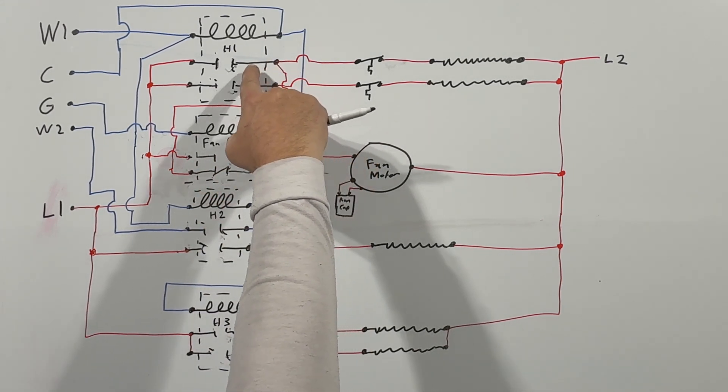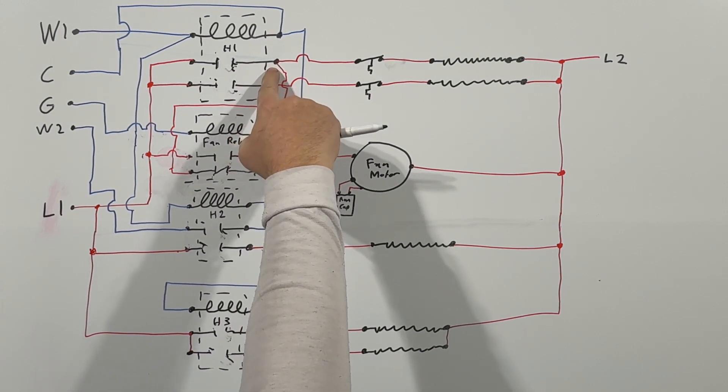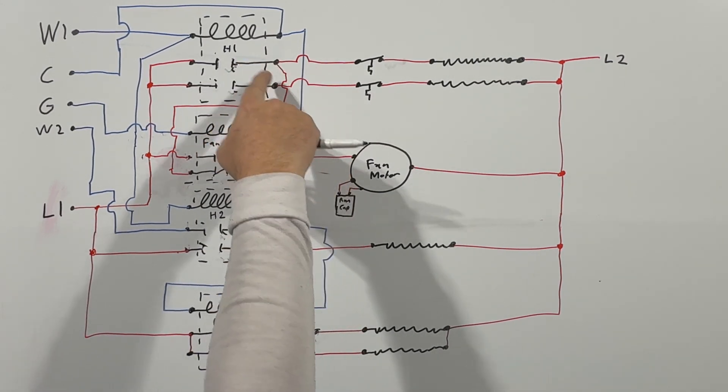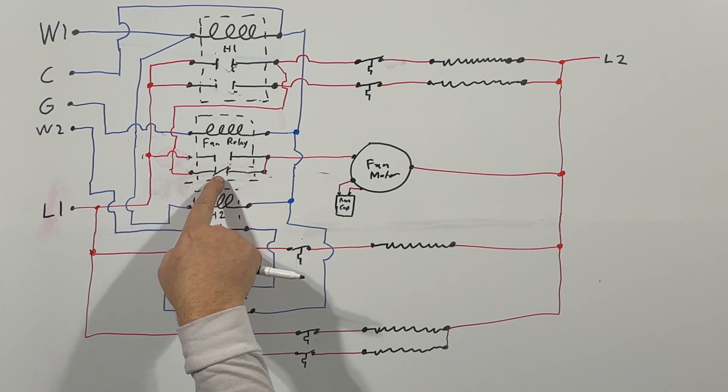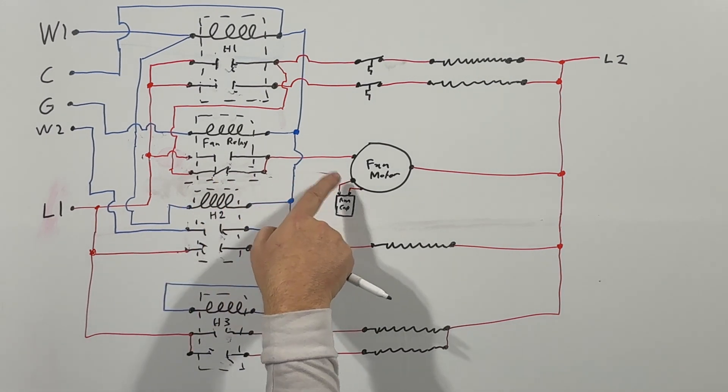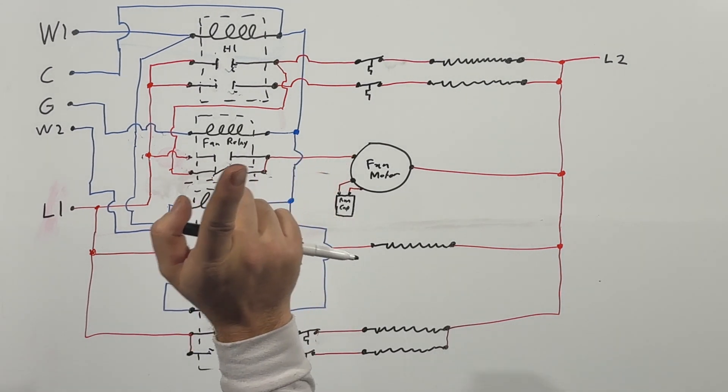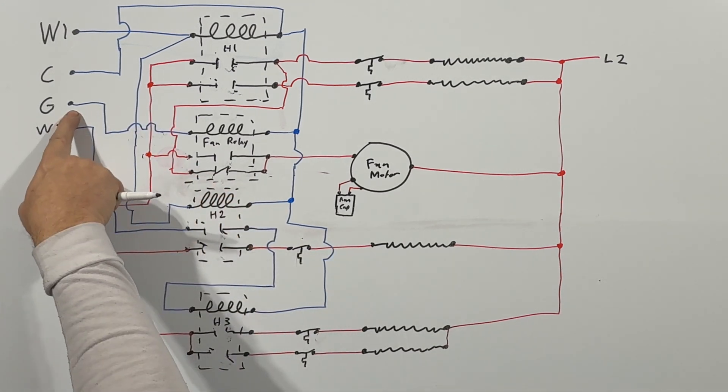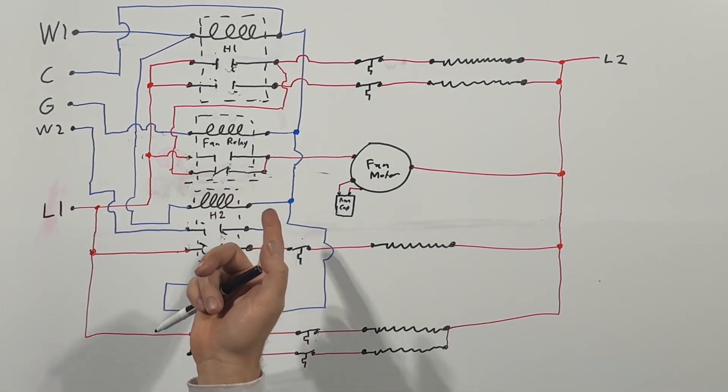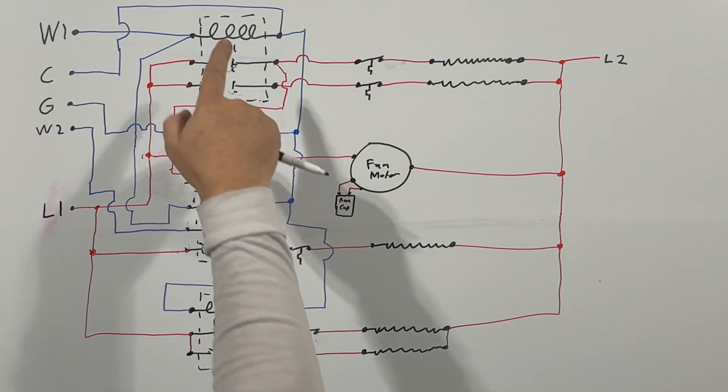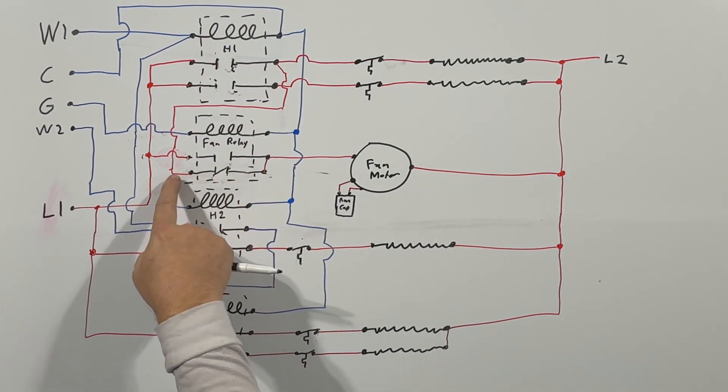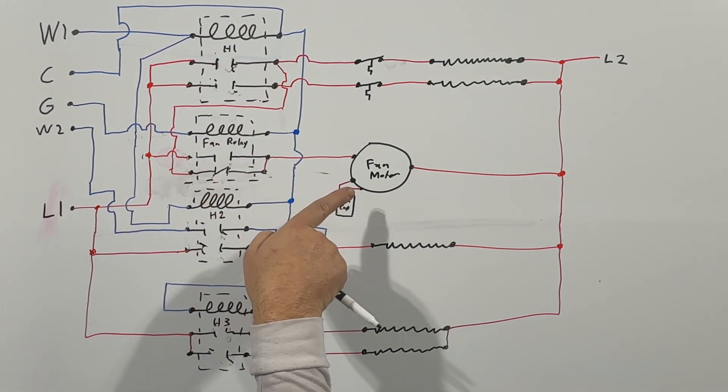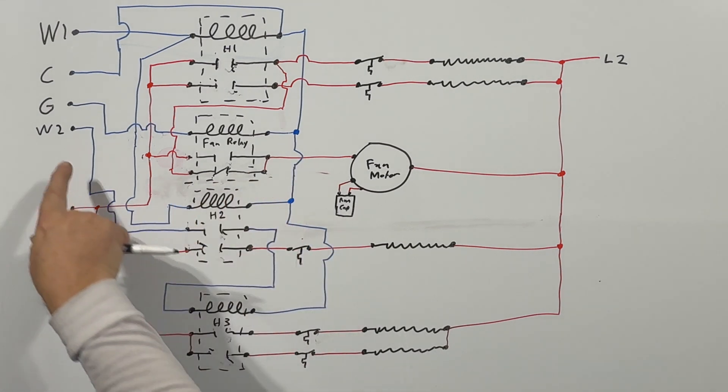Now if you look at our fan relay here, you could see we have a normally closed contact and a normally open contact. So high voltage or line voltage is supplied by H1 on the load side. So if that's energized, we get high voltage which would travel through the normally closed contact and energize your fan. But if we want to run just our fan, so we energize G, well how is that going to work?